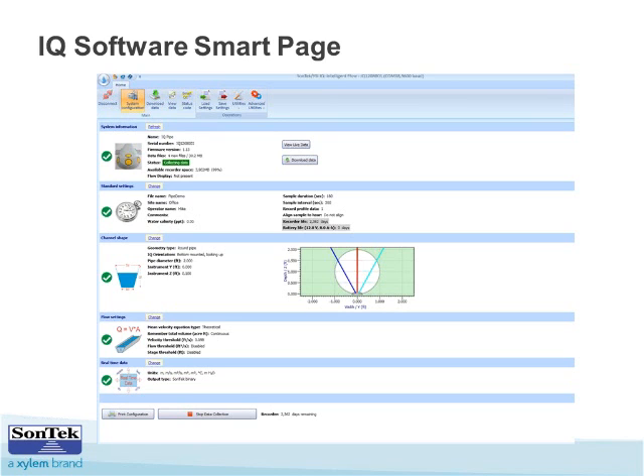One thing up here in the system information that I think everyone will find useful, especially if you've had experience using the older Argonaut platform or anybody's platform for that matter: if you look over View Live Data and Download Data, while the system is collecting data in run mode, you can click View Live Data while interfacing with the instrument and look at instantaneous data of the last measurement sitting in the buffer, without having to stop it, download, and process it. That's a very good point.